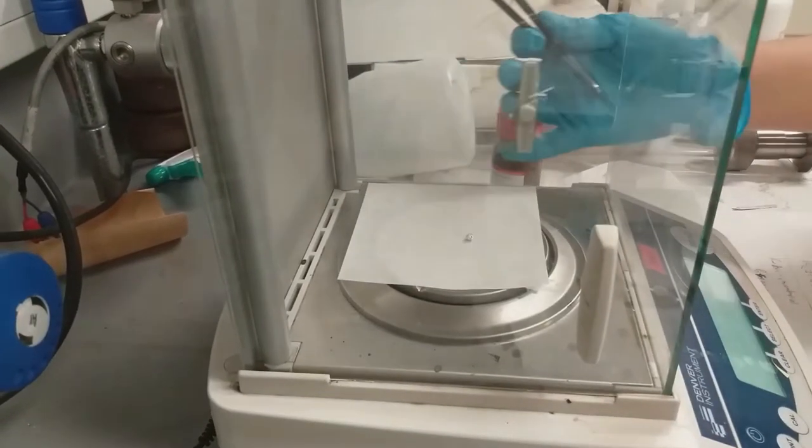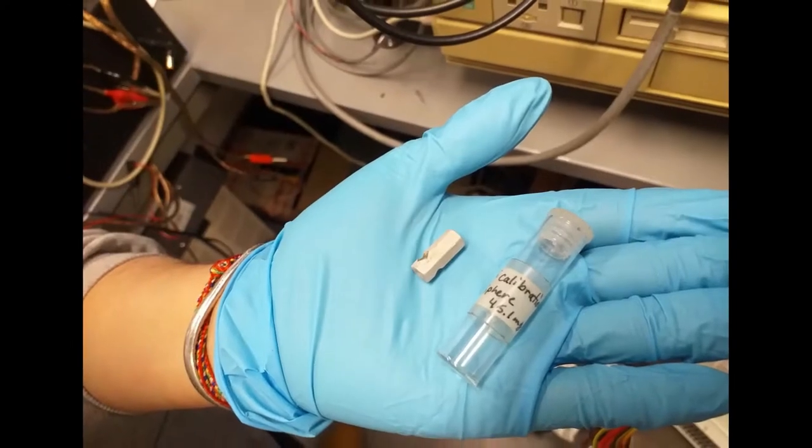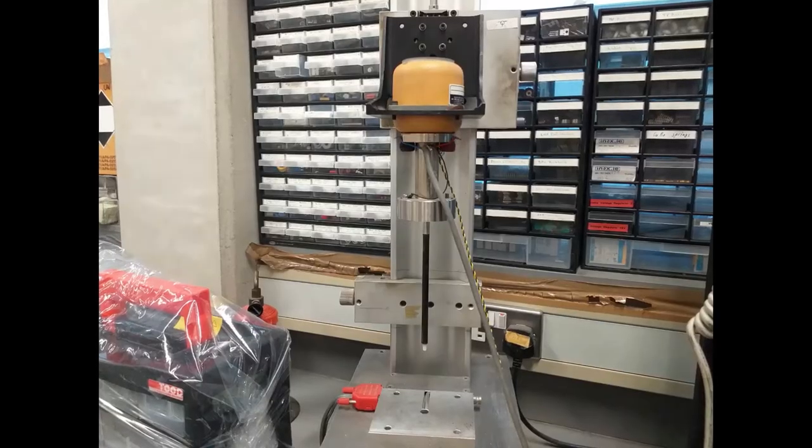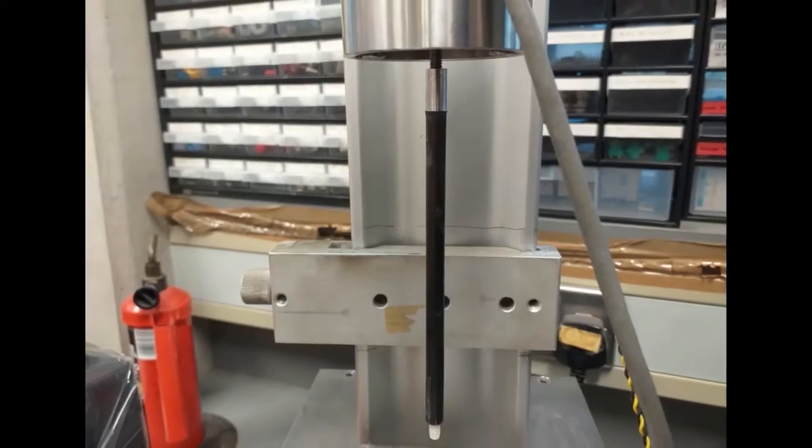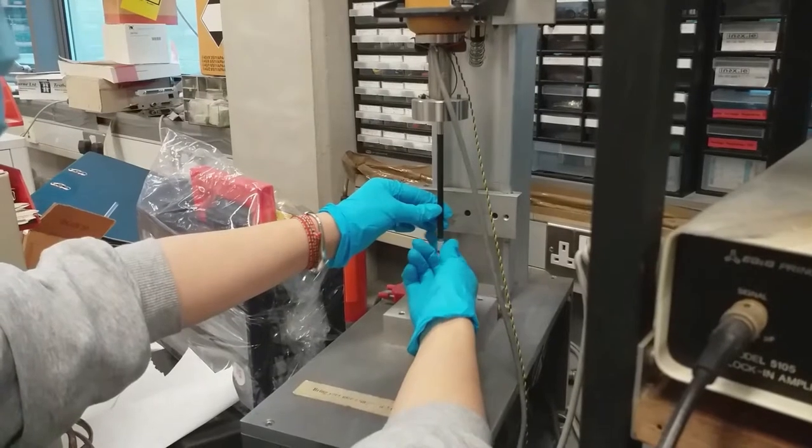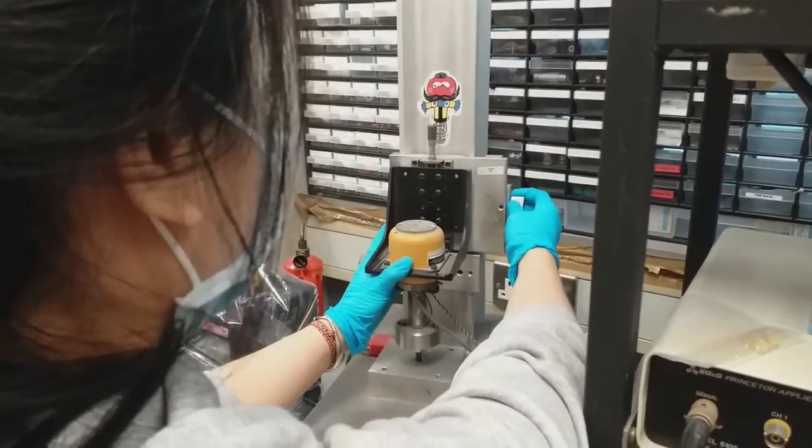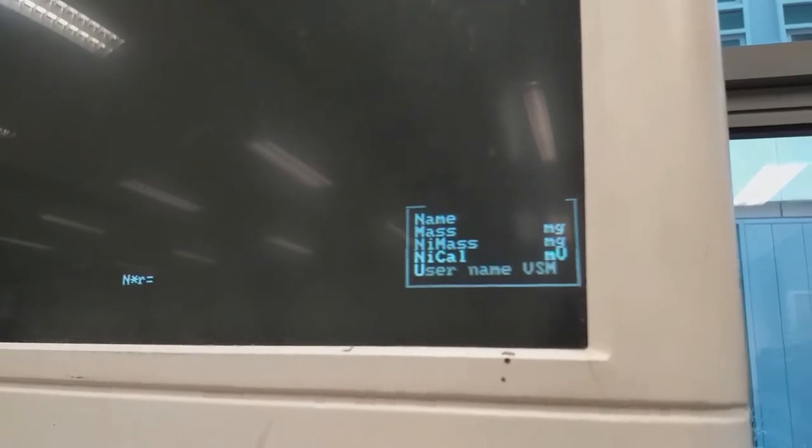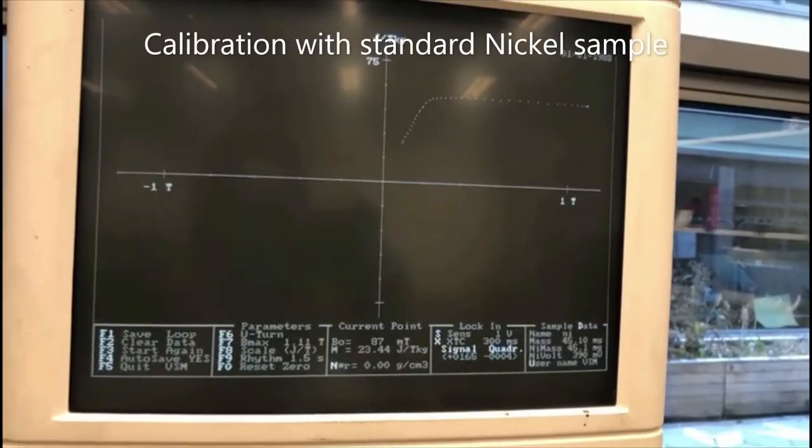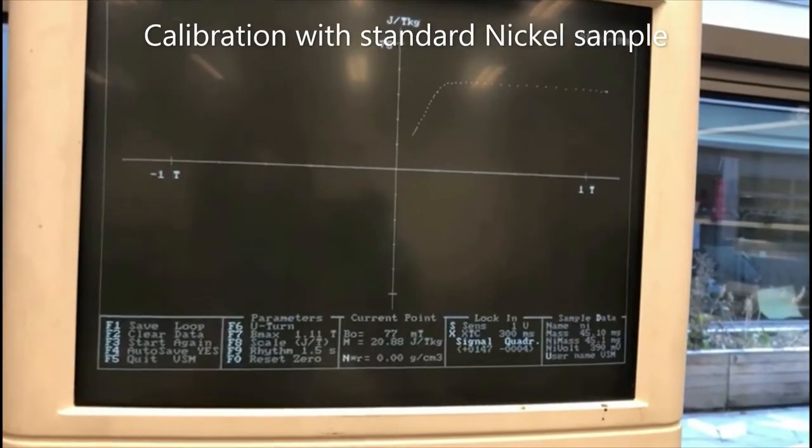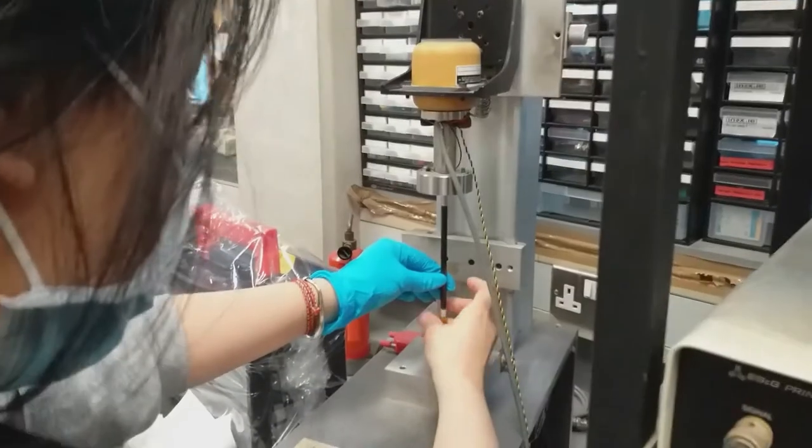Then we obtain a small ball to put on the sample holder. In order to obtain reliable data, we need to load the standard sample nickel to do the calibration. This is the vibration rod. The sample holder will mount on it. Then we move the rod to the center of the magnetic field gently.